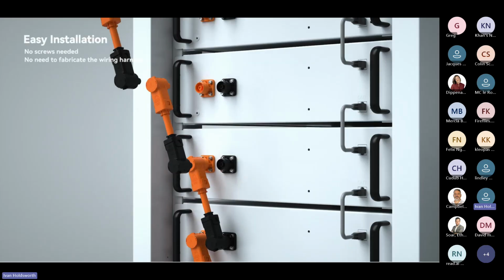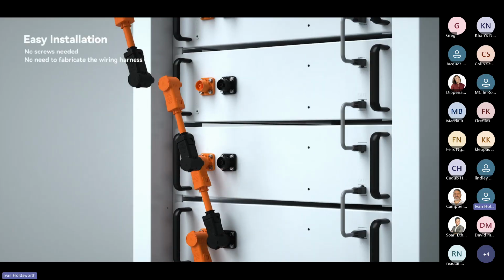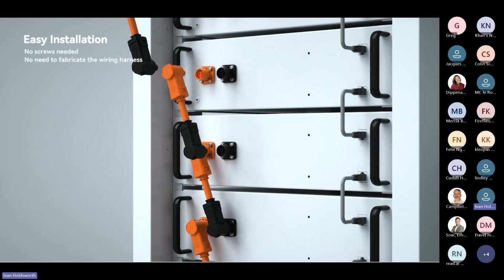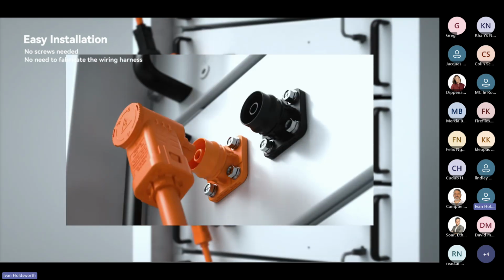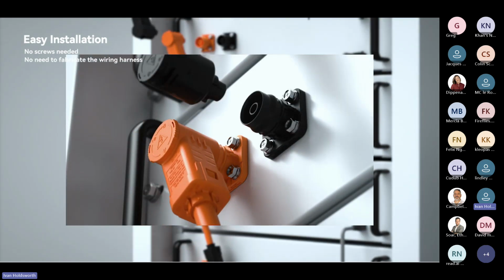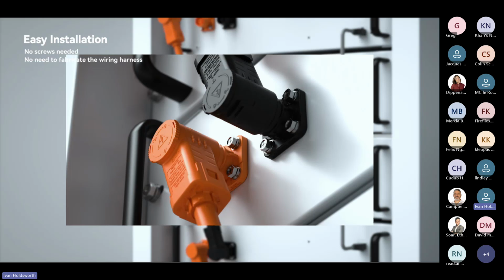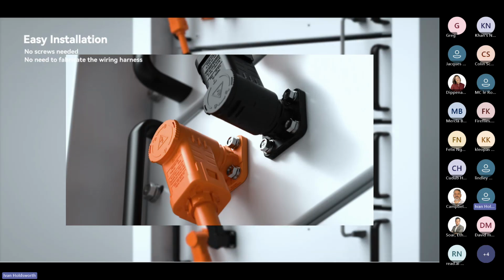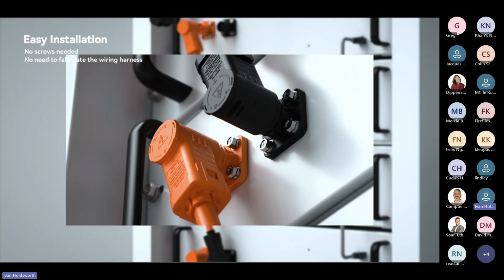You can see the series connection on your batteries. So what will happen is, as you adjust the number of modules in your tower, you'll adjust the voltage of that tower as well. So you can adjust the voltage to make sure it's within the operating range of your inverter battery input.